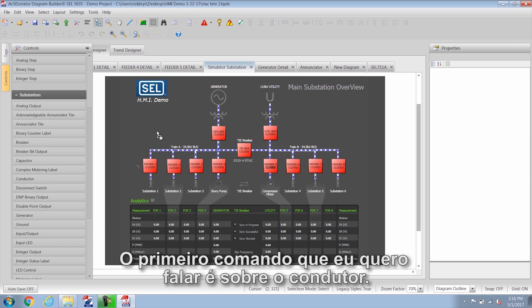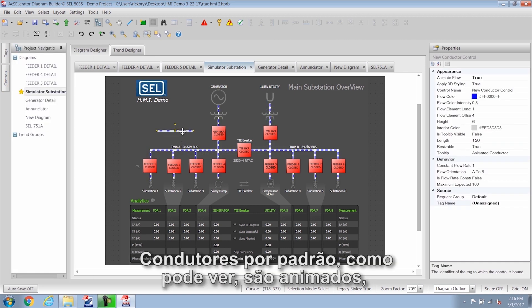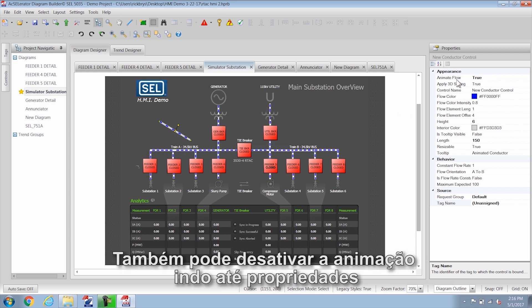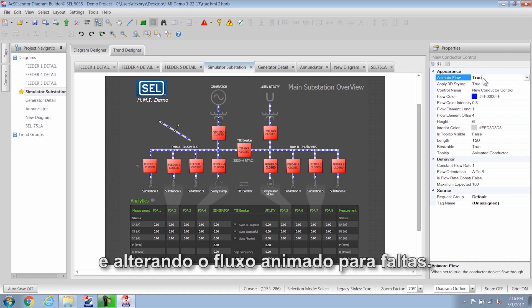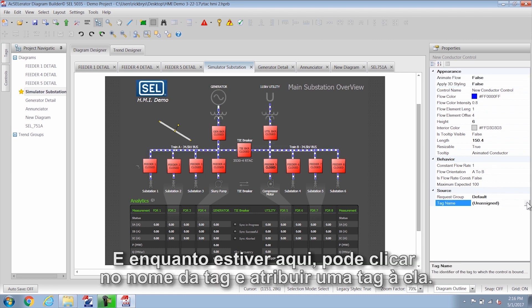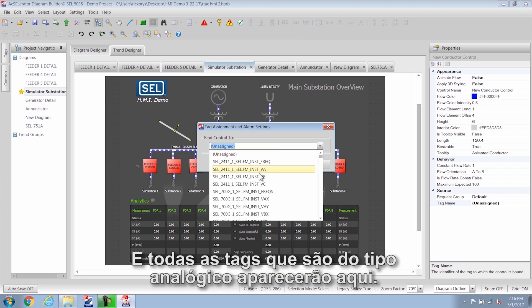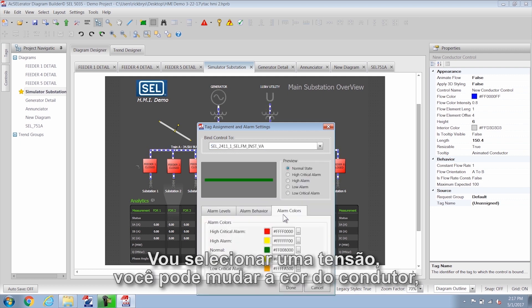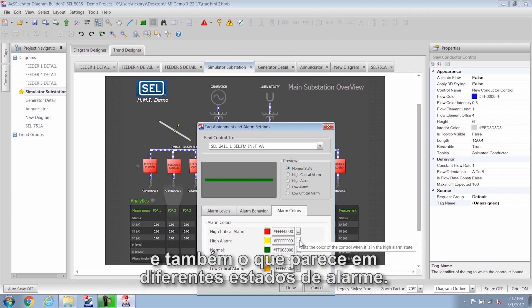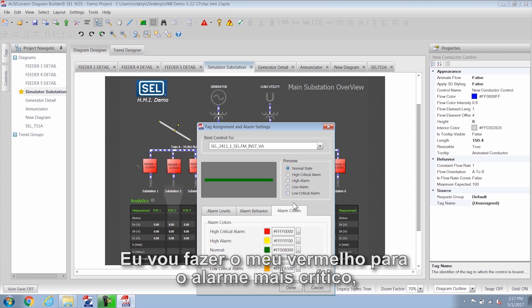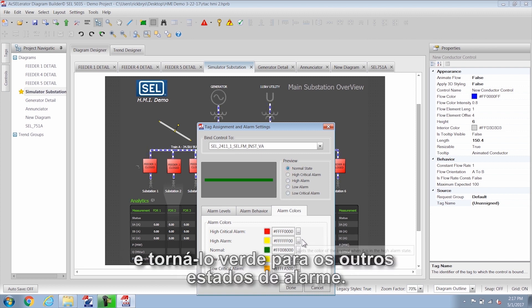The first control I want to talk about is the conductor. Conductors by default are animated, and you can change the size and rotate the conductor to whatever angle you need. You can also turn the animation off by going to the properties and changing the animated flow defaults. I like to change the 3D styling defaults as well. While in there, you can click on the tag name and assign a tag to it — all analog type tags will show up here. You can also change the color of the conductor and what it looks like in different alarm states, so when the alarm goes above a certain value it will change color. I'll make mine red for the critical high alarm and green for the rest of the alarm states.